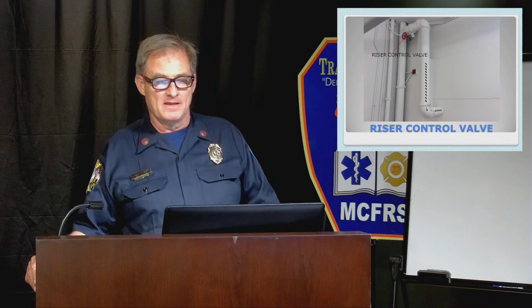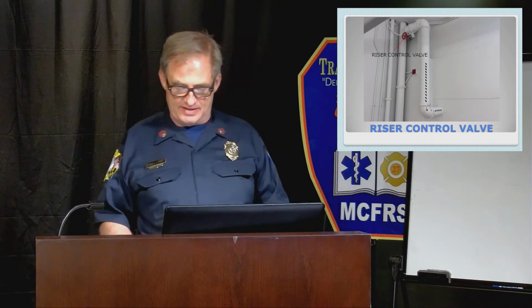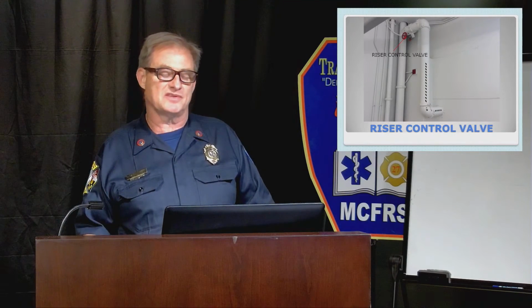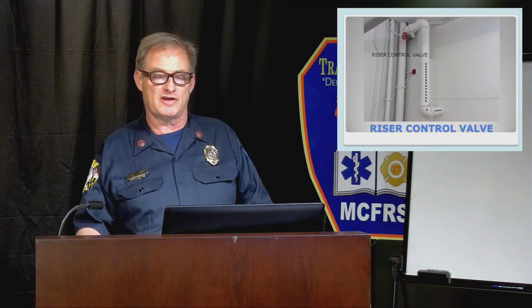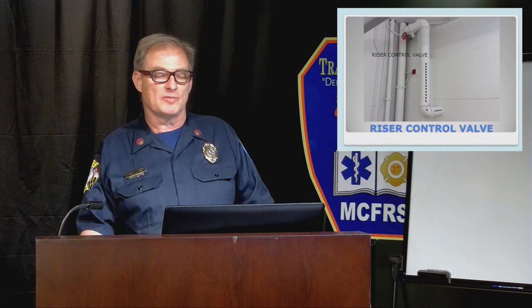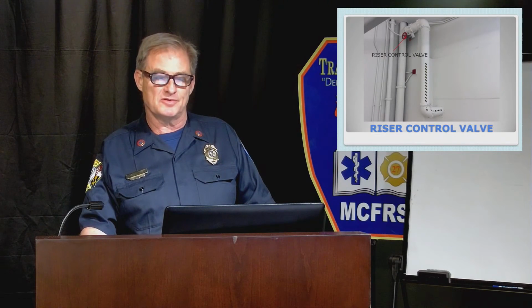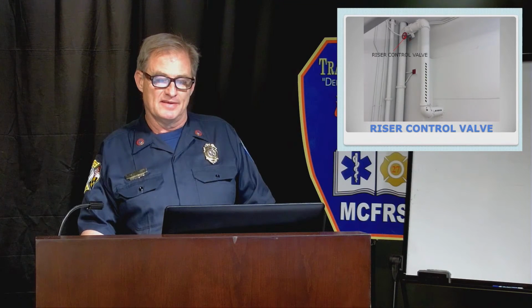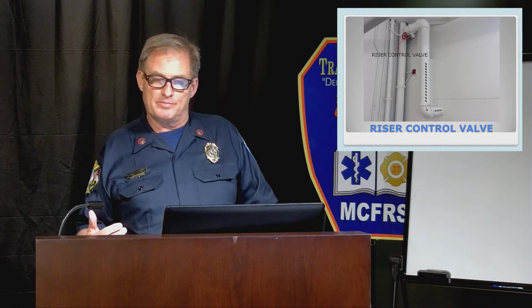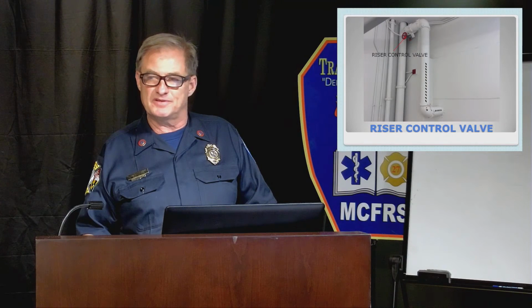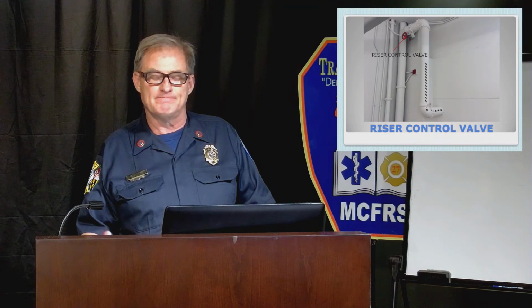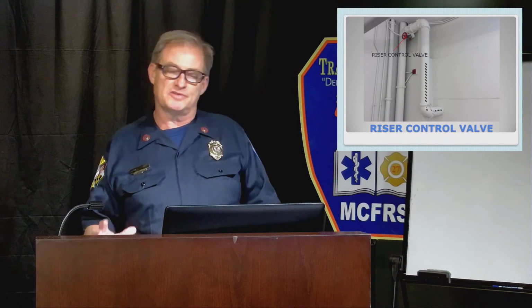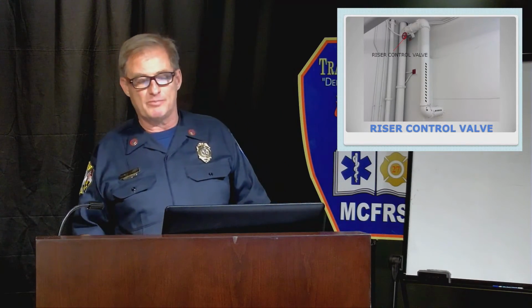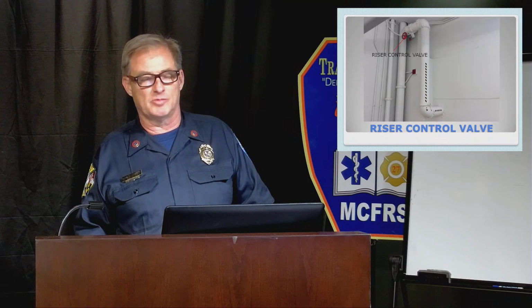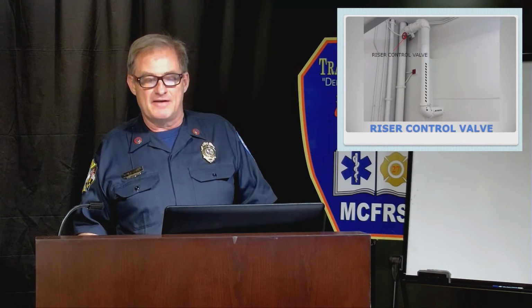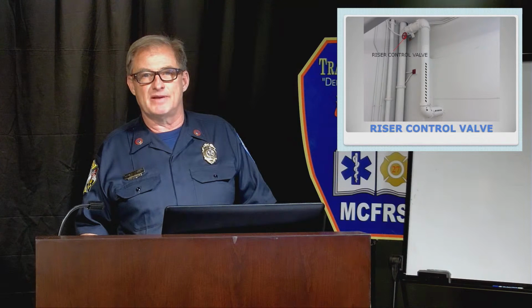Now in this case it was an older building, and they did not do any upgrades that made them put in pressure reducing fire hose valves. In one of my other presentations we talked about those. I think everybody's been trained that if the FDC fails, you have the option of pumping into the riser, right? If you have a pressure reducing fire hose valve, you could pump all day long at unbelievable pressures. It is never, ever going to let water into that standpipe. It's not going to happen.